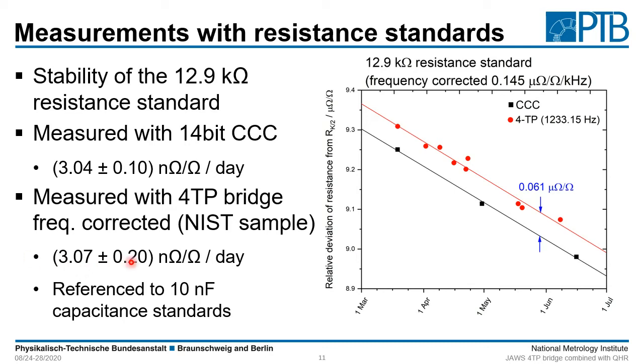We can also see a slight deviation between the CCC data at DC and our AC measurement, even though we correct the frequency response of our reference resistance. This deviation is small but we want to shrink it further. It could be that we have a different frequency correction for our standard which has to be remeasured, or there is some systematic effect in our system which we have to find.